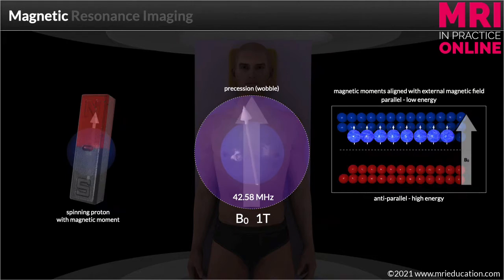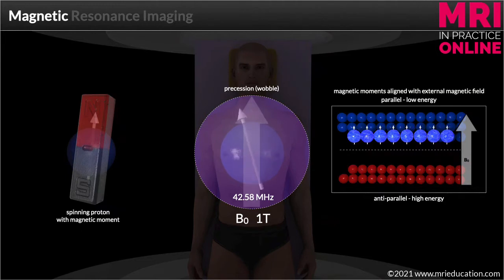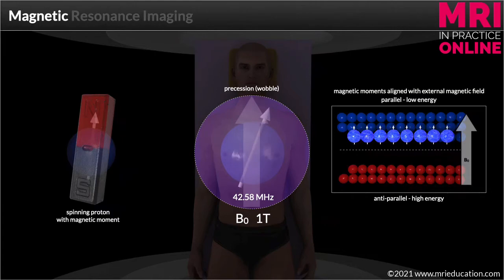In MRI we call this little system a spin packet, or spin for short. The official term used to describe this wobble is precession. The speed at which the vector precesses is also dependent on the external field and it's known as the Larmor frequency. This frequency is proportional to the flux density of the external field. At one tesla the frequency is 42.58 megahertz. At 1.5 teslas it increases to 63.87 megahertz and so on. So this is the reason that an MRI scanner uses a magnet — it allows us to create a net magnetic vector from the hydrogen nuclei.